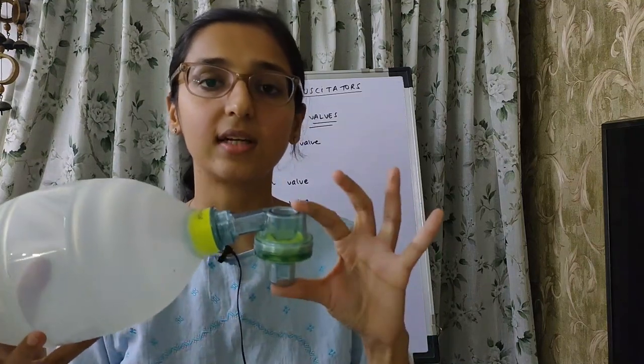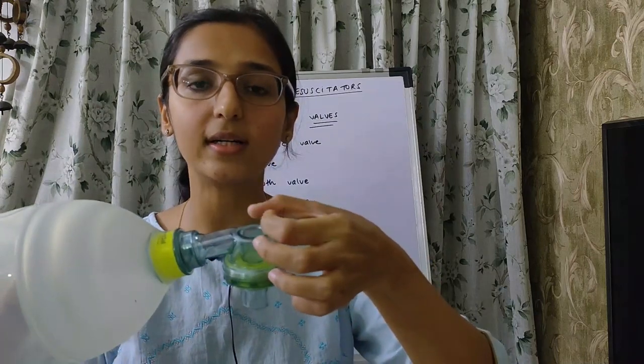There is another component — a pressure limiting device, also known as a pop-off valve. In this larger resuscitator, there is no pop-off valve. However, some resuscitators have a spring-loaded disc at the housing as a pop-off valve. At a certain pressure, this valve pops off and causes escape of extra gas to the atmosphere, preventing ventilation with very high inspiratory pressures. The maximum pressure is 60 cm H₂O in adults and 45 cm H₂O in pediatric patients.